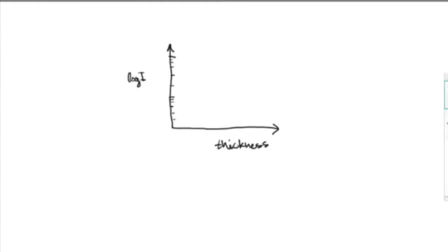Another way this beam hardening manifests is a change in the half-value layer as the beam penetrates. You can visualize it this way. If the beam starts up here at some initial intensity, and this is a log linear plot, it would drop here to, let's say, half the intensity in some thickness that's equal to 1 half-value layer. If the beam were to keep attenuating that way, with standard attenuation, you would see this type of plot extending down in log scale, but it doesn't.